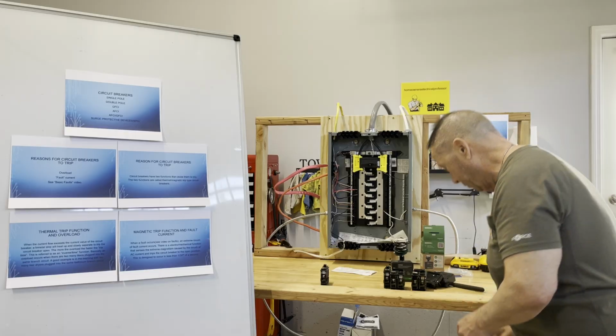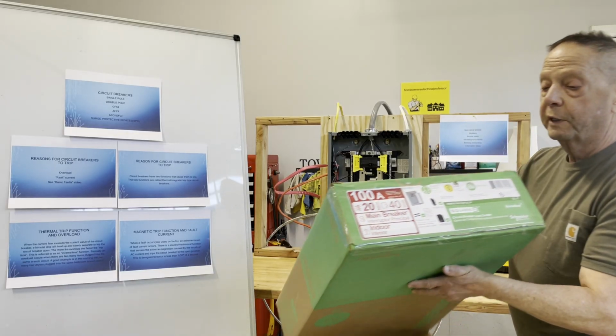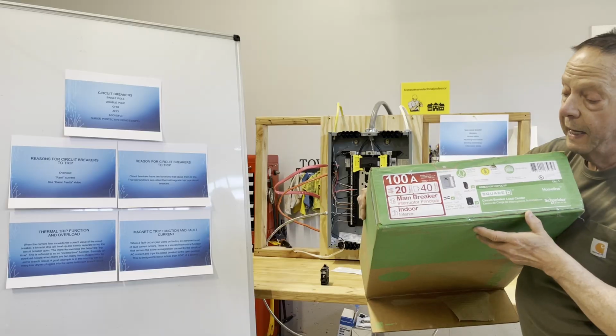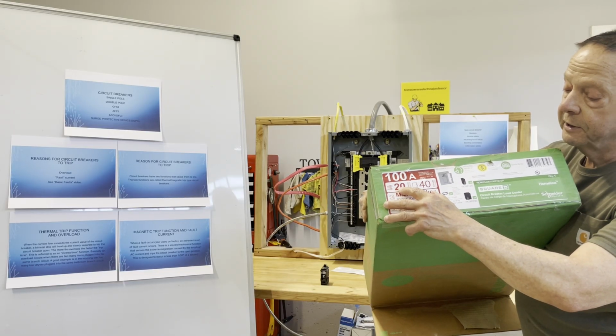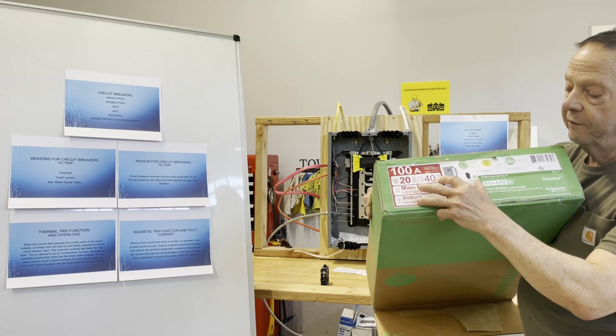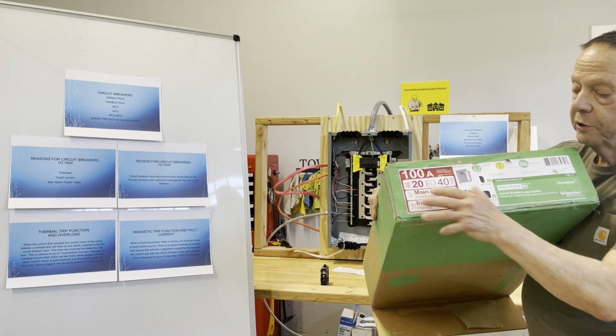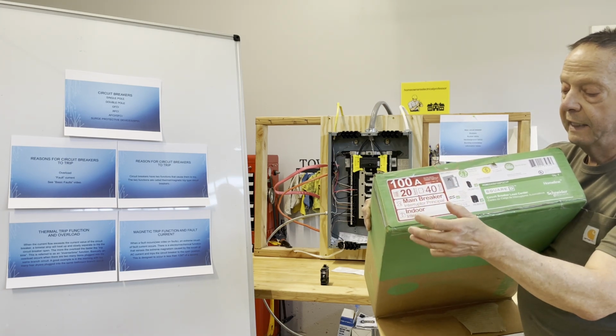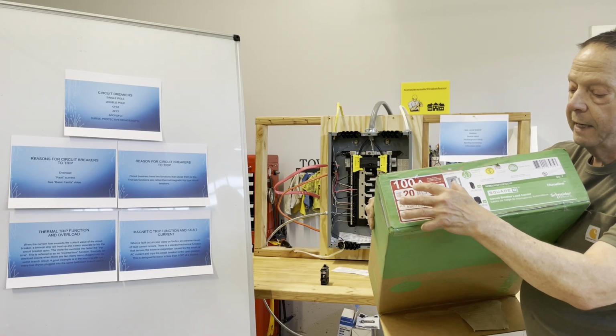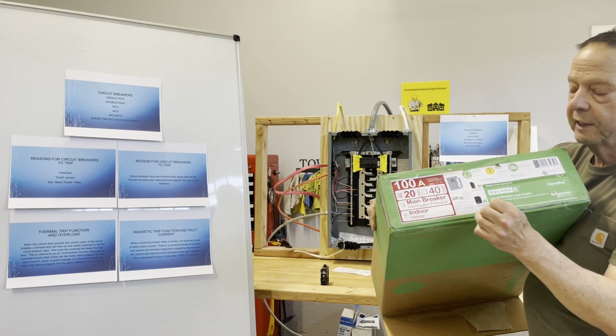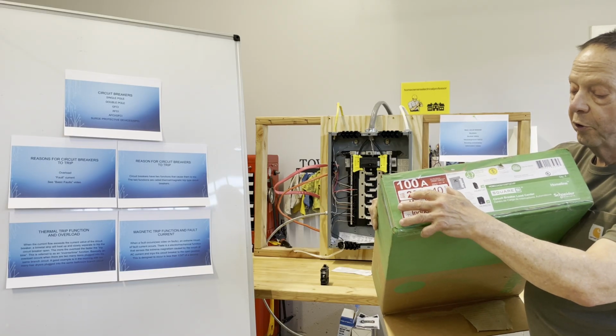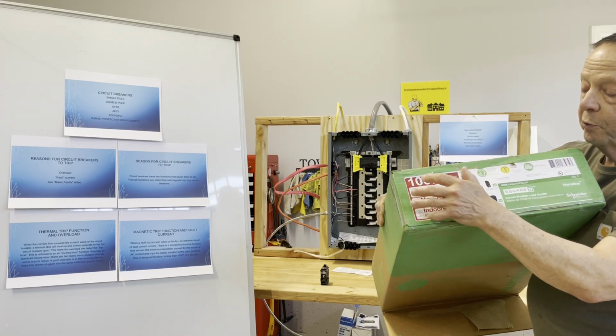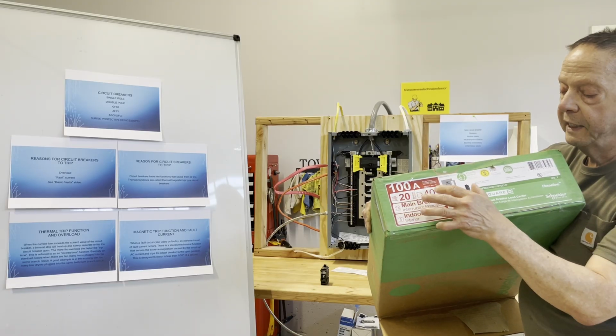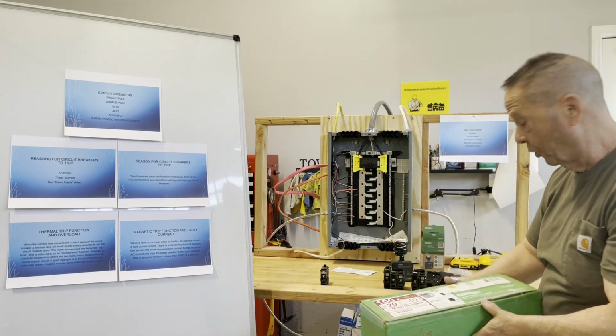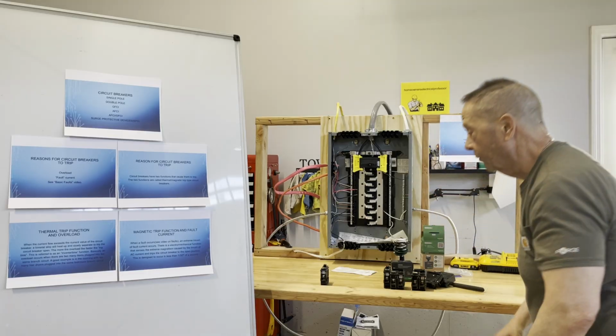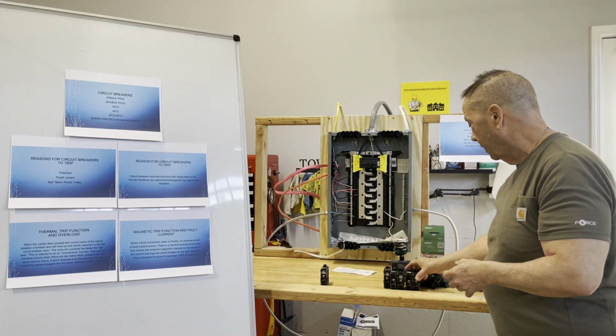The other thing you can look for is on your electrical panel. This one here says it's 20 spaces and it'll accommodate 40 circuits, all right? If you go to the big box stores, what they mainly sell today is what's 100 amp, 20 spaces, 40 circuits. 150 amp will say 30 and 60, and a 200 amp panel will say 40 and 80. It's a lot of circuits to put in the house. Okay, so that is a little introductory to circuit breakers.